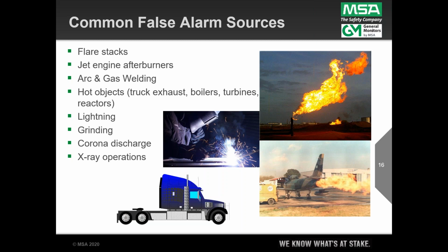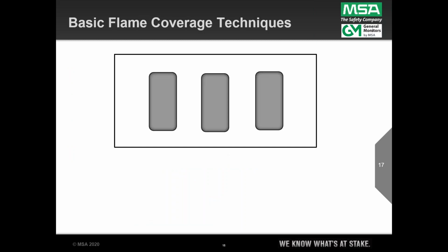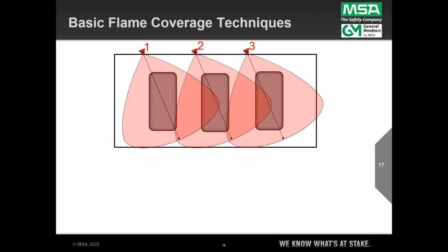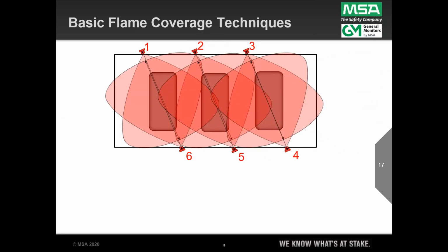I like to talk about coverage techniques with these flame detectors. So this is just an example of a three-compressor building, basically three compressor skids, maybe a recip engine compressor. The most common way of protecting these types of skid-mounted equipment is to put detectors in opposing corners, looking back towards center. So we've got 1, 2, and 3 in that corner, and then detectors 4, 5, and 6 come back in the opposite corner. Here we are using two detectors to cover each of these compressor skids, and we've got all five sides covered by these two detectors.